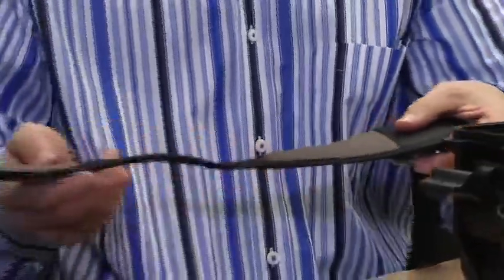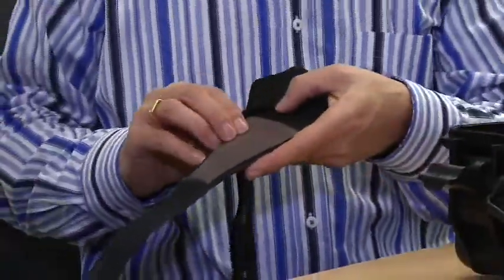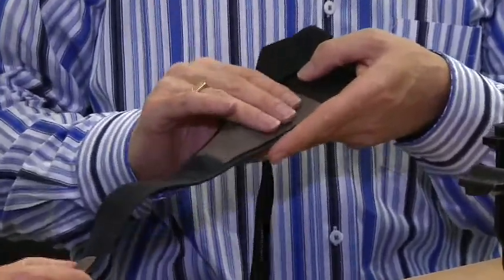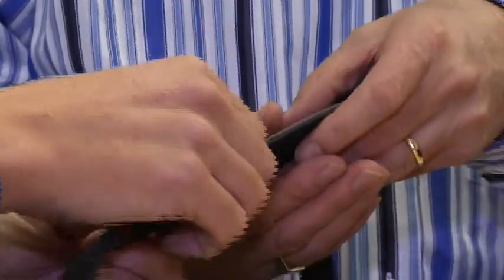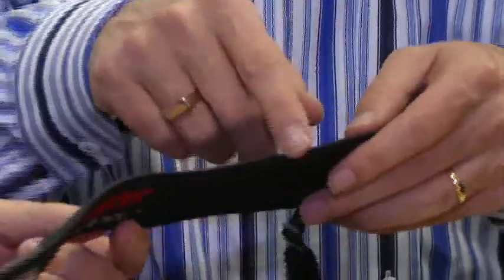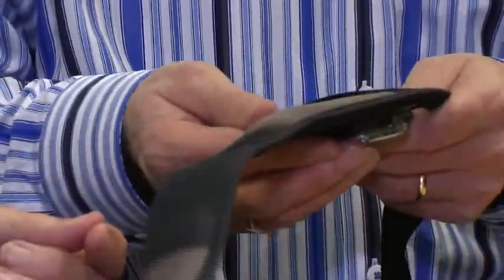And this essentially clips into this receptacle, and this is part of Zephyr's smart fabric technology. So this is the ECG sensors, which go on the chest here, and then here we've designed a respiration sensor. And what this is, it's a capacitance pressure sensor. So as the person breathes, they'll apply pressure to this sensor pad, and then that'll go through to a signal in the actual BioHarness device.